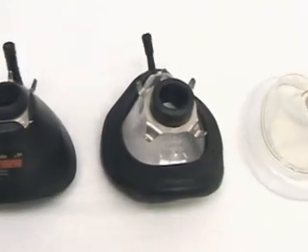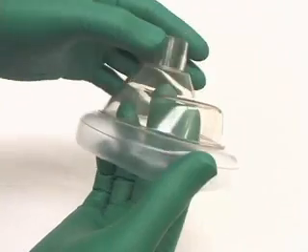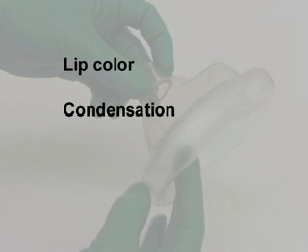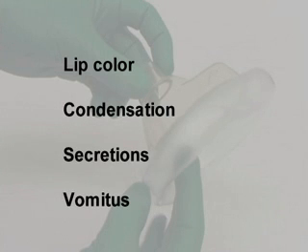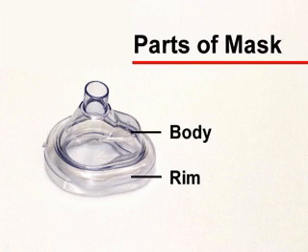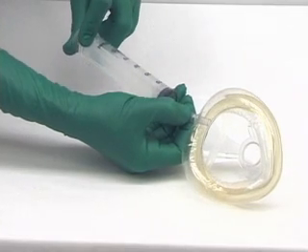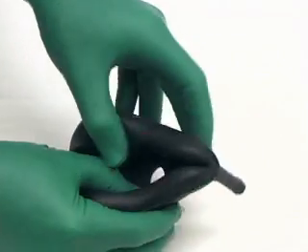There are many types of face masks, varying in design, size, and construction materials. Transparent masks are preferred because they allow for inspection of lip color, condensation, secretions, and vomitus. Face masks consist of three parts: the rim, the body, and the connector. The rim of the mask provides the seal with the face. Many masks have an inflatable cushioned rim which creates a better seal with facial contours. Some masks have a malleable body which can be molded to the face, thus reducing dead space.